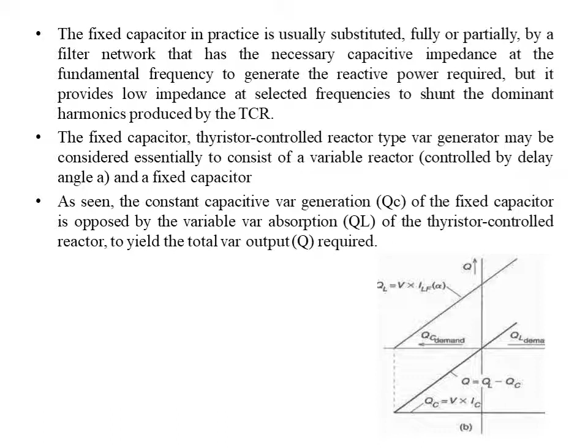At maximum capacitive VAR output, the thyristor controlled reactor is off, that is, at angle alpha equal to 90 degrees the thyristor is off and the reactance of the capacitor is maximum, or VAR generation from the capacitor is maximum. So to decrease the capacitive output, the current in the reactor is increased by decreasing the delay angle or firing angle alpha. So here we have two conditions.